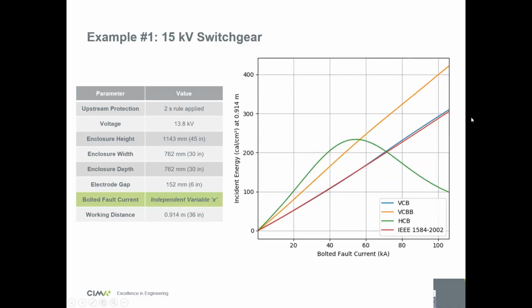Then this is the big one. So the fault current. When you plot your energy against your fault current, what you see here is that at about 50 kA you have your peak for HCB, but your peak for other configurations is much higher. So if your fault current is, let's say, below 70 kA, then your HCB would be higher, but above that your HCB would be lower.